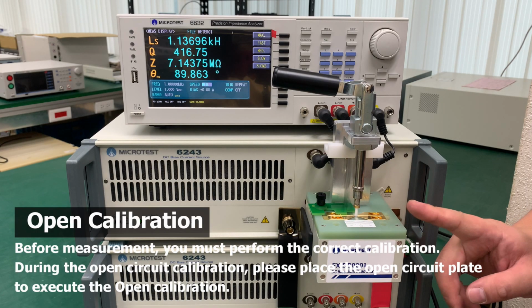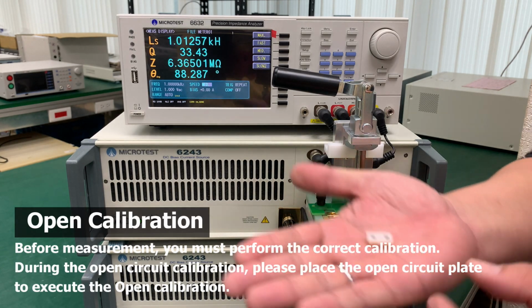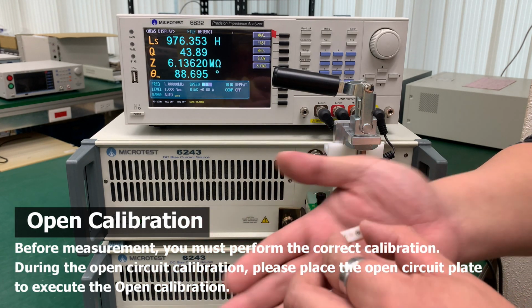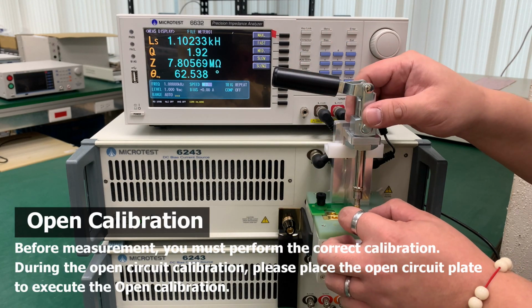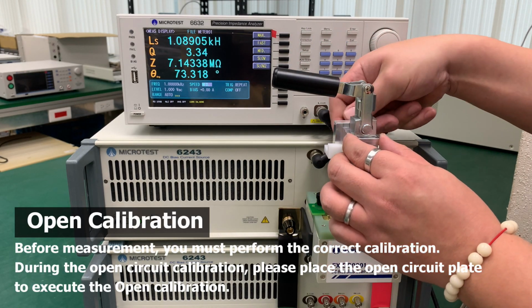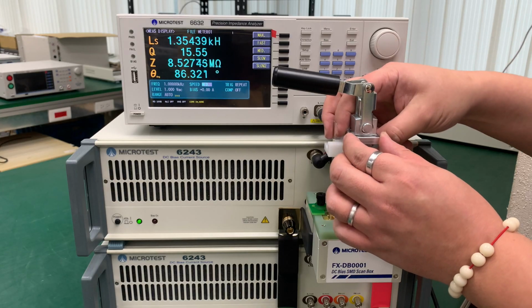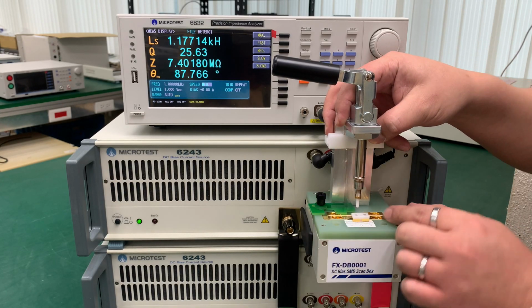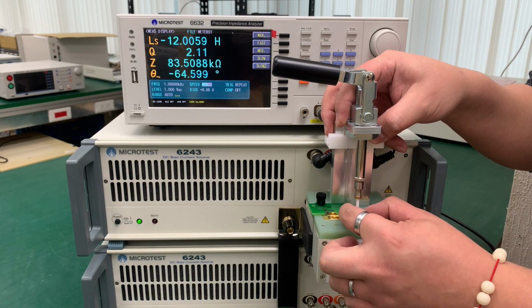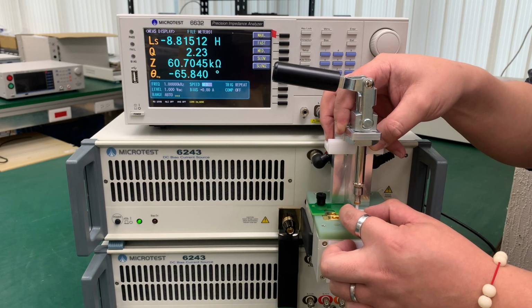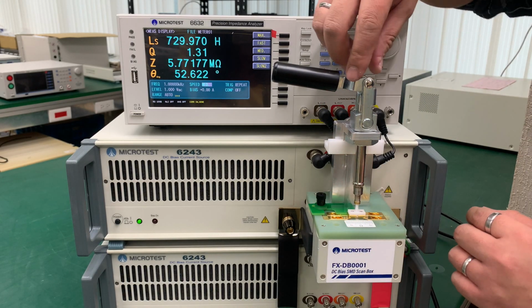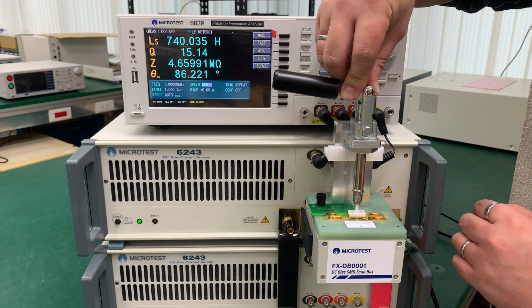Before measurement, you must perform the correct calibration. During the open circuit calibration, please place the open circuit plate to execute the open calibration. First, loosen the nut at the back of the fixture, then lift the fixture's probes upward. After placing the open circuit plate, press the probes down, and simultaneously tighten the nut at the back of the fixture.